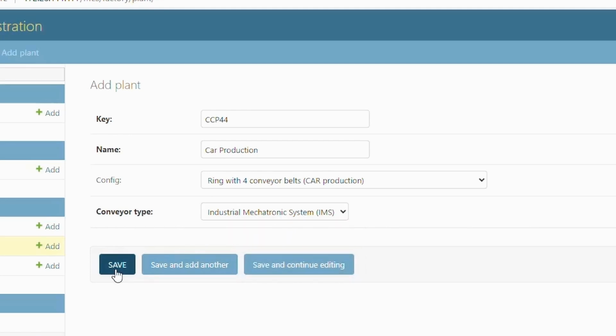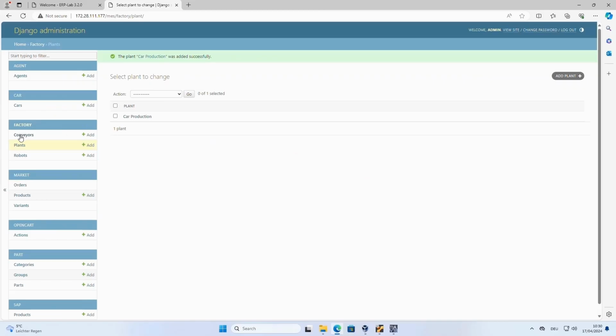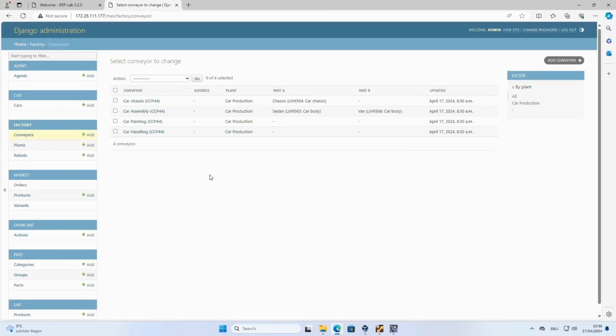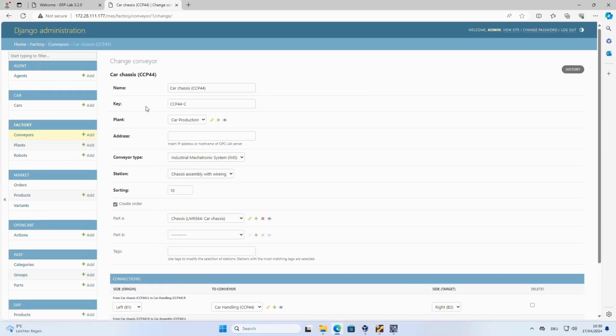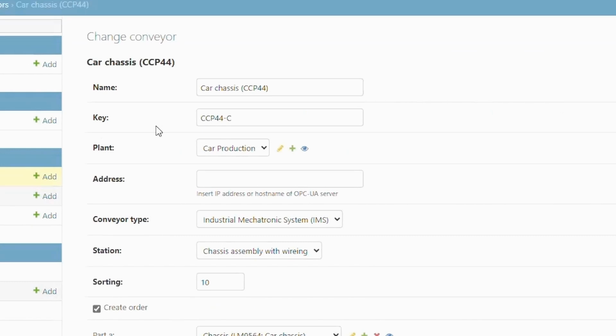Now we switch to the Belts tab, which is already pre-configured due to the template. Were you able to use a template which exactly matches your system? So we only need to enter the IP addresses of the belts. Click on the belt to do this. In the settings, a station name and key were initially assigned. Additionally, the newly created production line has already been selected. Under Address, we enter the corresponding IP address of the belt. The addresses of the belts start at 172.28.111.11 for the first belt and increase by one number for each subsequent one.